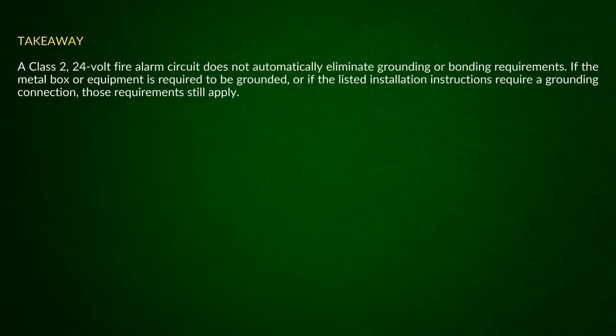So as a good example, when you have a Class 2, 24 volt circuit, that does not automatically mean you're going to eliminate any grounding or bonding requirements. So that's where I put in here, just to finish this off: if the metal box or equipment is to be grounded, or if the listed installation instructions require a grounding connection, those requirements still apply. That's it.